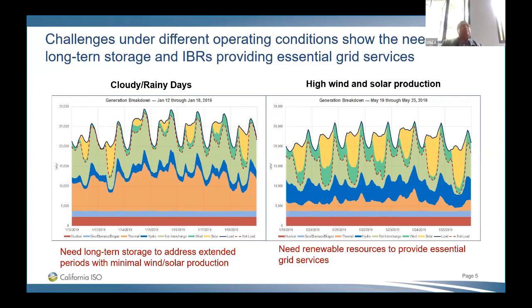Now this also creates challenges for us, especially with hydro. If you have a lot of hydro in spill conditions, you get zero ancillary services from the hydro fleet because they tend to operate pretty close to PMAX. When you operate close to PMAX, they won't back off to provide downward ancillary services, and likewise they have nothing to move up.